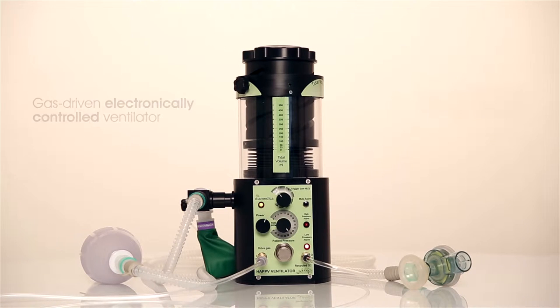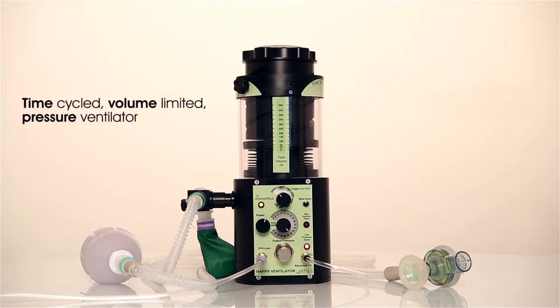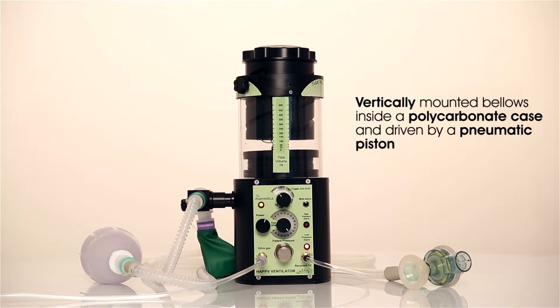The ventilator is a gas-driven, electronically controlled ventilator. It can be used in operating theaters in conjunction with a suitable anesthetic apparatus or for longer term ventilation in ICU. It is a time-cycled, volume-limited pressure ventilator with vertically mounted bellows inside a polycarbonate case and driven by a pneumatic piston.